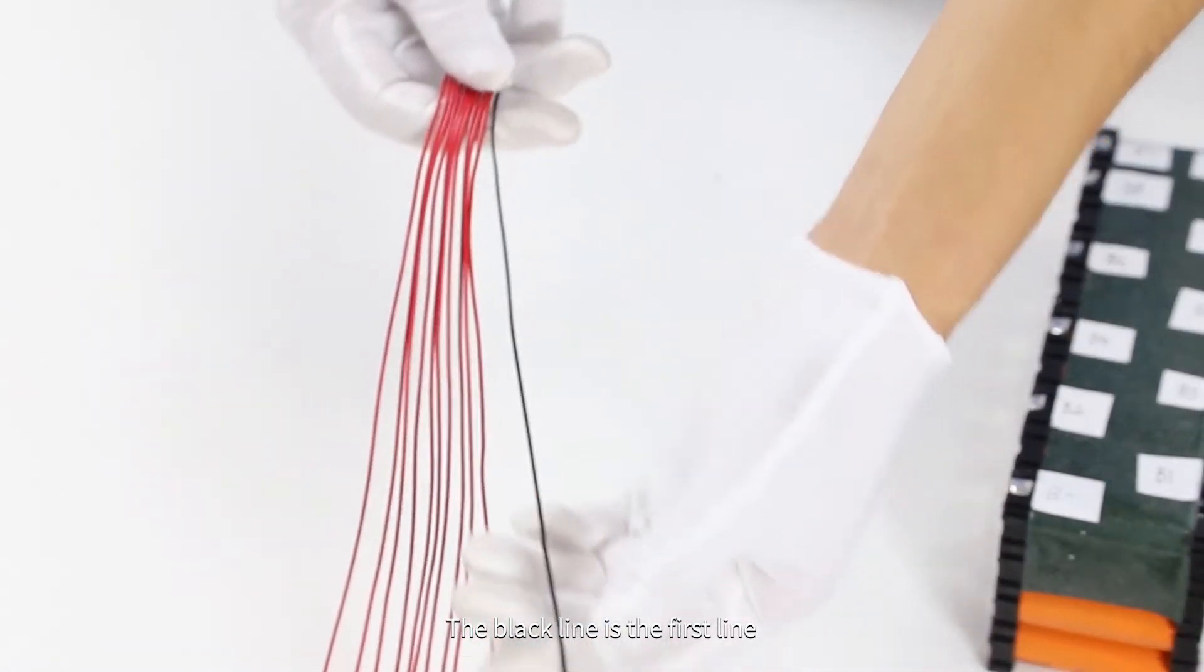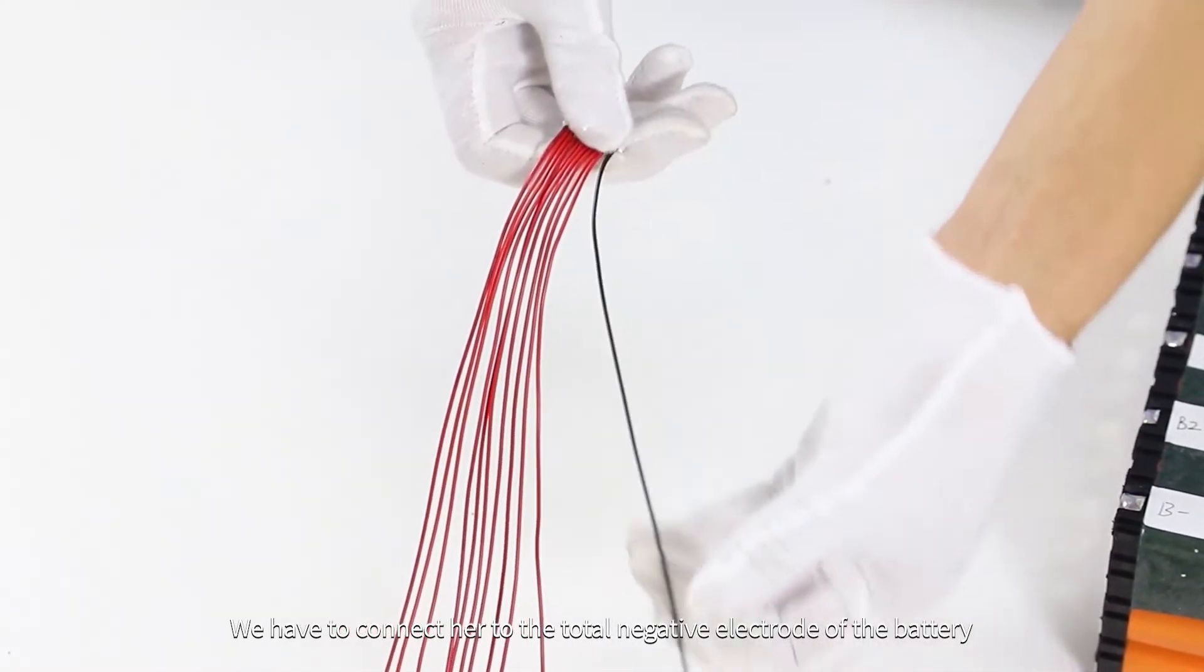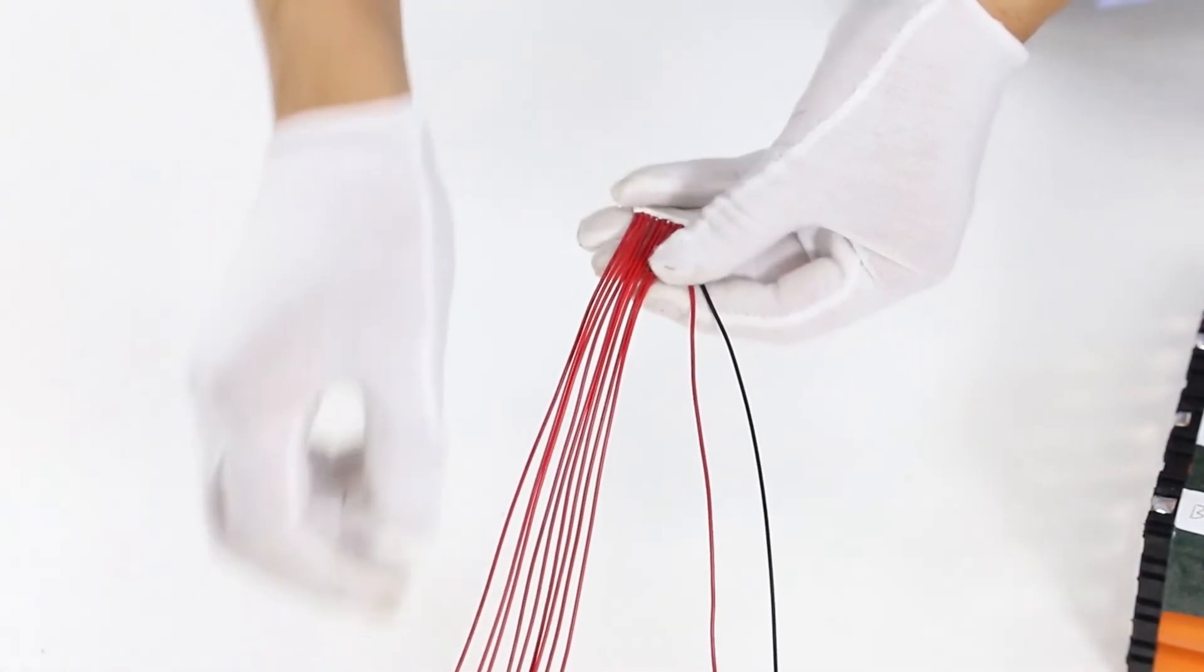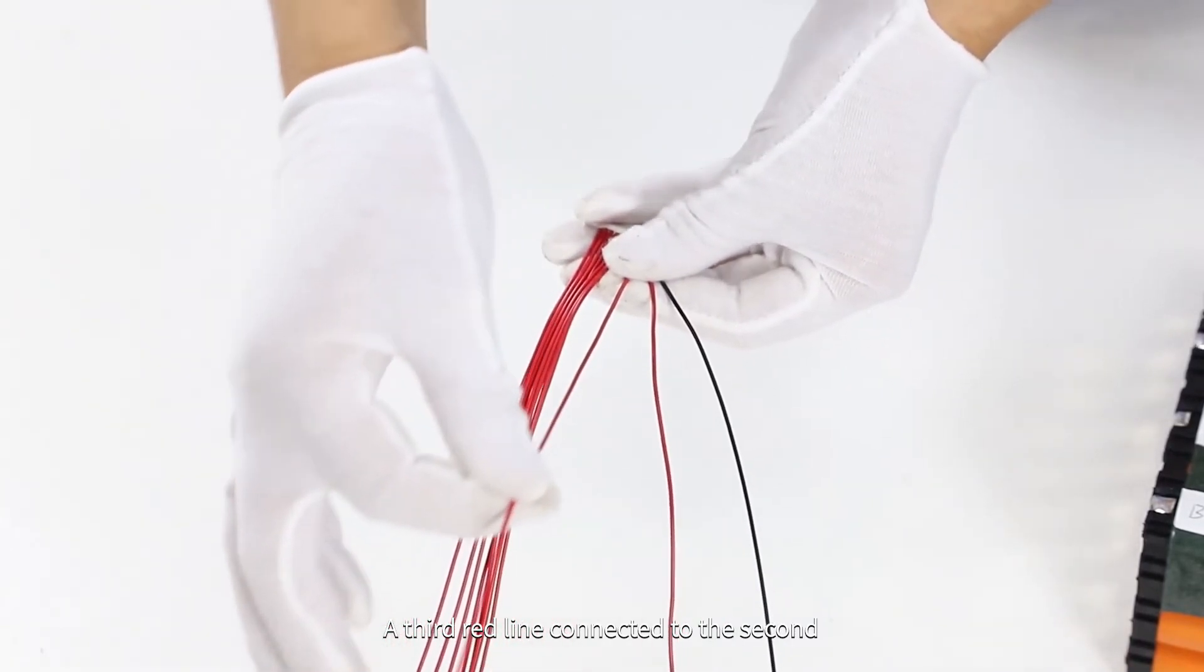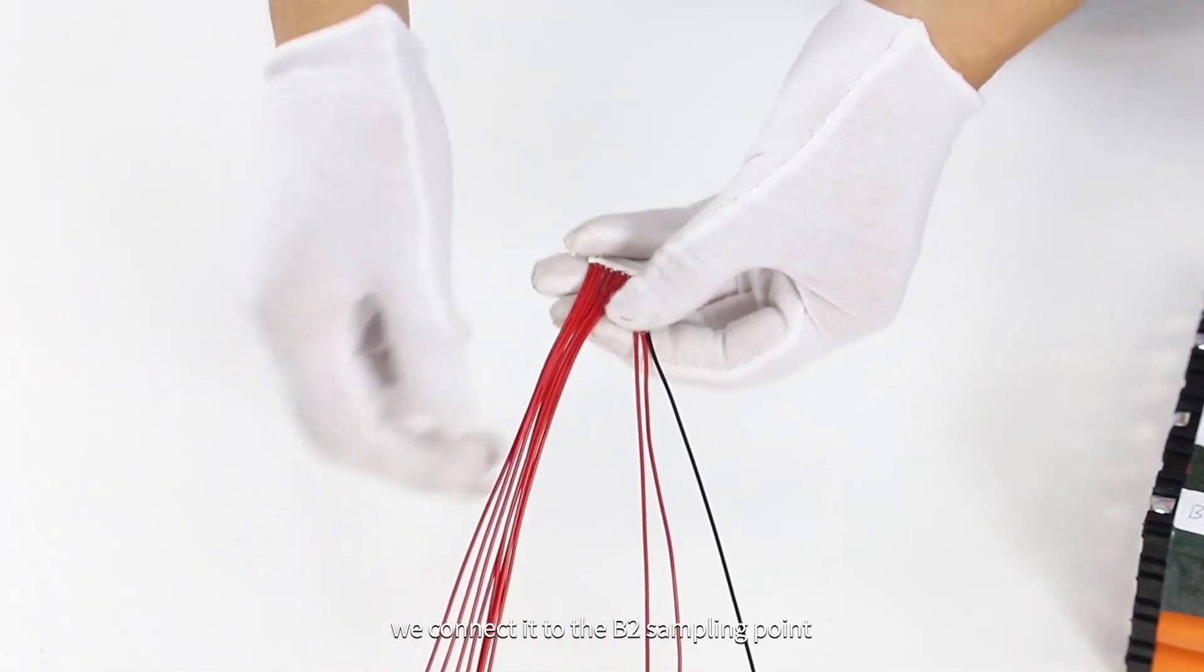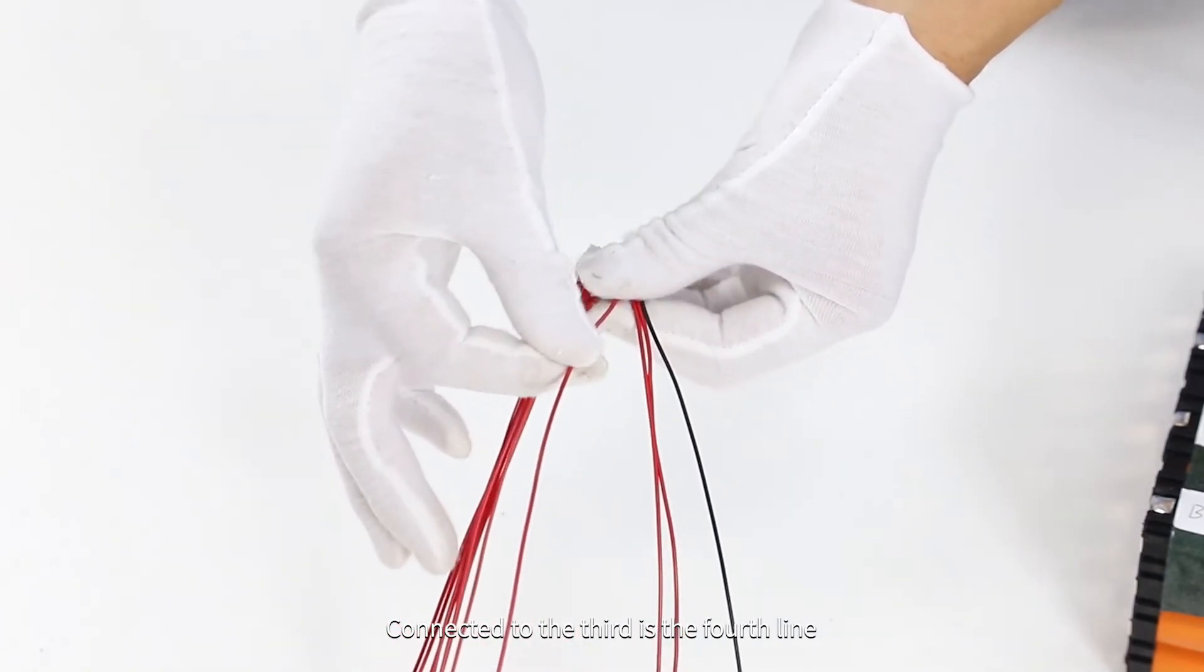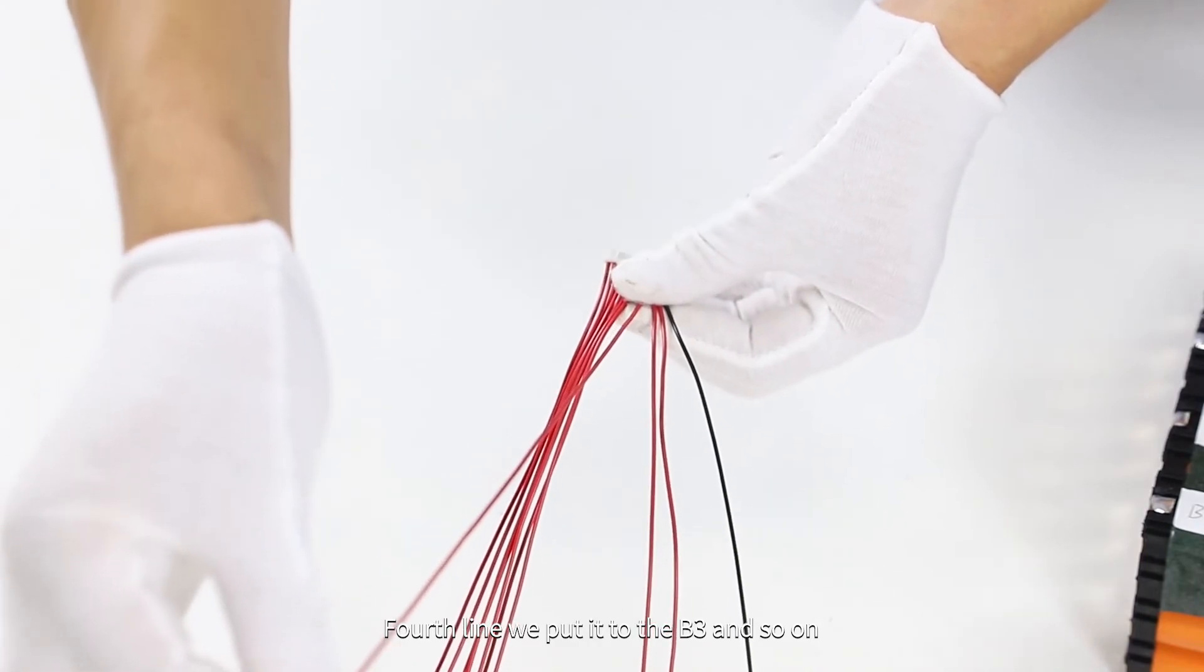The black line is the first line. We have to connect it to the total negative electrode of the battery. The second line is red, we'll take it to B1. The third red line we connect to the B2 sampling point. Connected to the third is the fourth line. Fourth line we put it to B3, and so on.